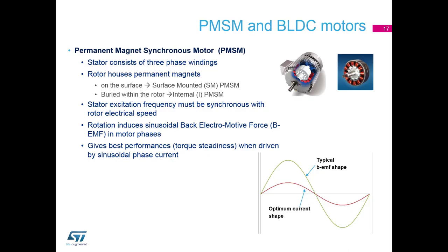Okay, now let's talk about the Permanent Magnet Synchronous motors and Brushless DC motors. First, Permanent Magnet Synchronous motor, PMSM. Its construction of the stator consists of three phase windings. Rotor is constructed from permanent magnets that can be either glued on the surface, which creates a surface-mounted Permanent Magnet Synchronous motors, or buried within the rotor, so-called internal Permanent Magnet Synchronous motors. The stator excitation frequency must be synchronous with the rotor electrical speed. The rotation induces a back EMF or back electromotive force, which has a sinusoidal shape. The motor gives best performance and torque steadiness when it's driven by a sinusoidal phase current from our power stage.